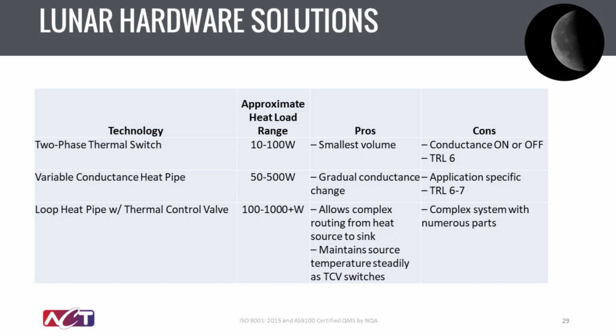As you can imagine, the length of the evaporating section and the condensing section drive how big the reservoir needs to be for that non-condensable gas, and how much gas it gets charged with is all very specific to the application, but when tuned appropriately to the application, it is a very great tool. And finally, loop heat pipes with the thermal control valve. This can do from about 100 to well over 1,000 watts, allow for that complex routing, vibration isolation, and maintain that source temperature steadily as the TCV switches back and forth, which we'll take a look at here shortly with the featured project. But one of the drawbacks is that it is a complex system with numerous parts.